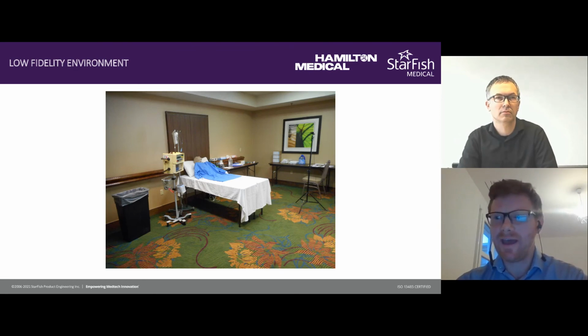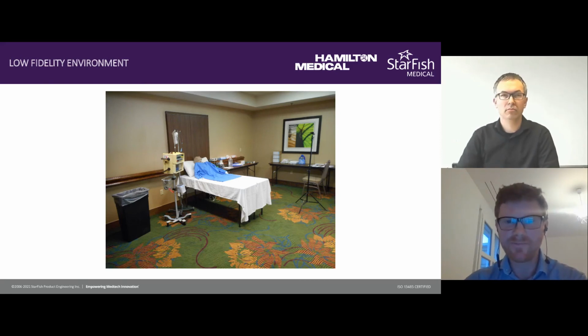And then from a summative perspective, you've got a lot of risks that are very low probability, like maybe 1 in 100,000 or 1 in a million, and you're never going to see them. But if you focus very finely on the device, because you're not in the scenario where you would be, you quite often see these popping up, and then they're very hard to mitigate or rationalize through root cause, because it's just a test artifact due to the low fidelity environment.